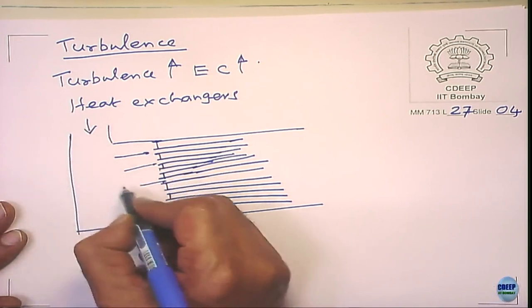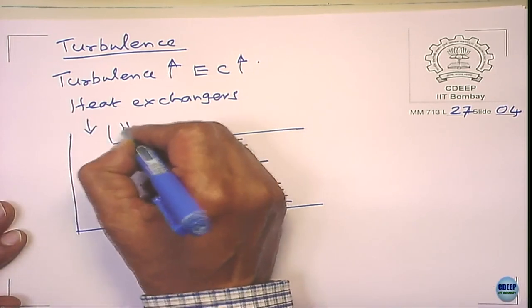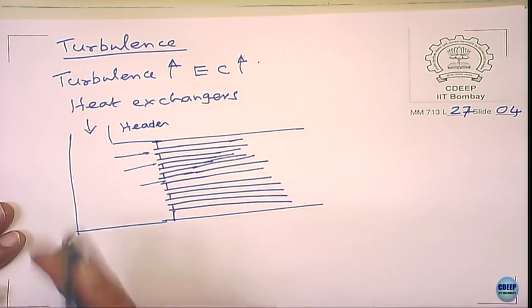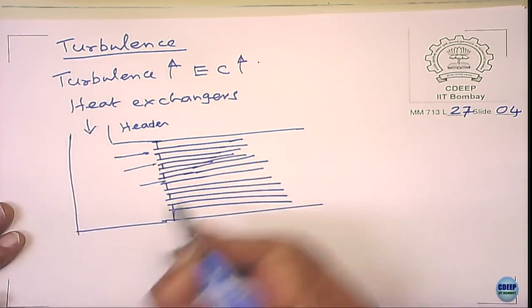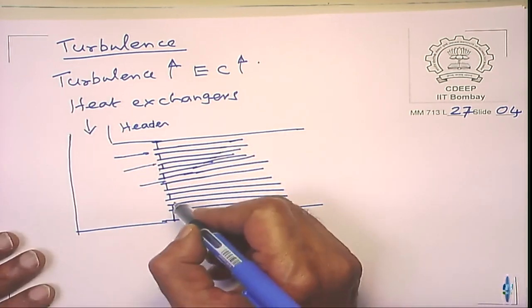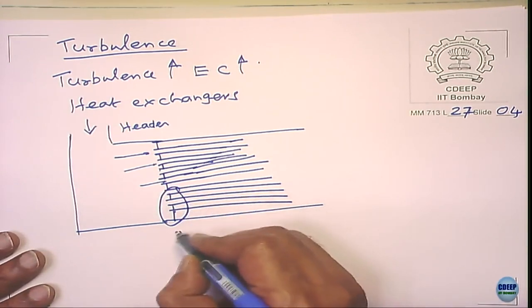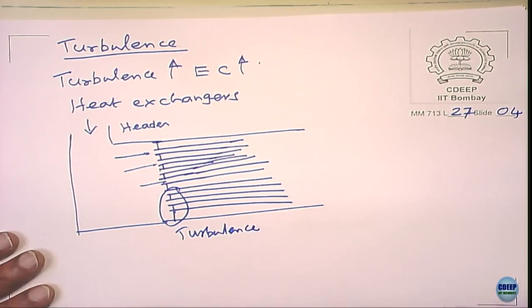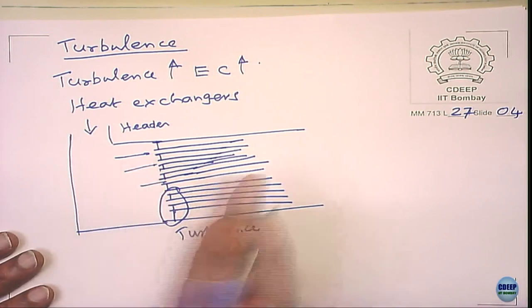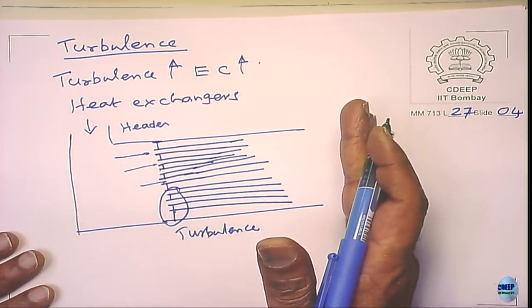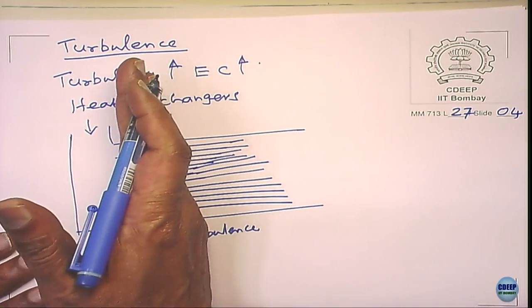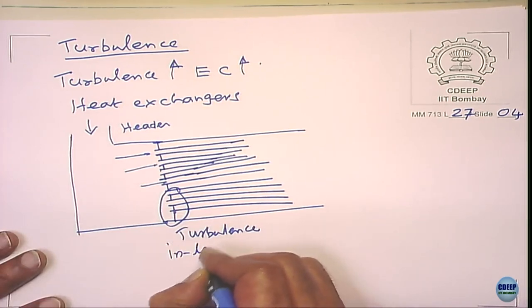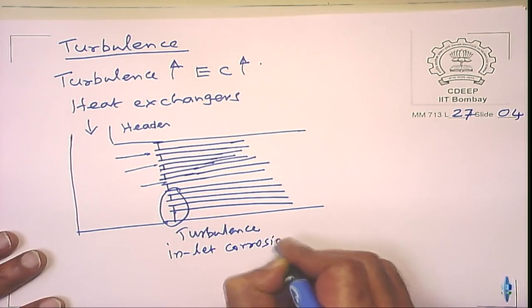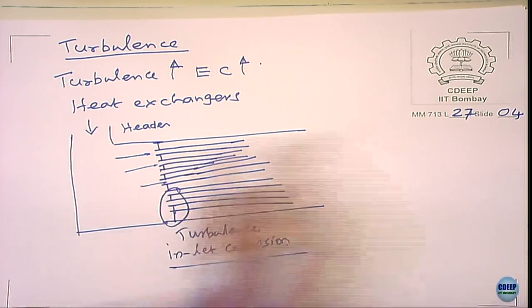So the liquid enters through the header, the shed, and there is almost a 90 degree turn as it enters. The maximum turbulence occurs at the inlet, and as it travels further inside, the degree of turbulence decreases. So the maximum damage in the heat exchanger occurs at the inlet. That is why it is called inlet corrosion. Now, how do you really avoid this?